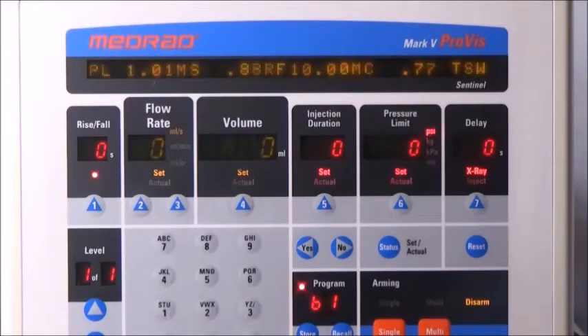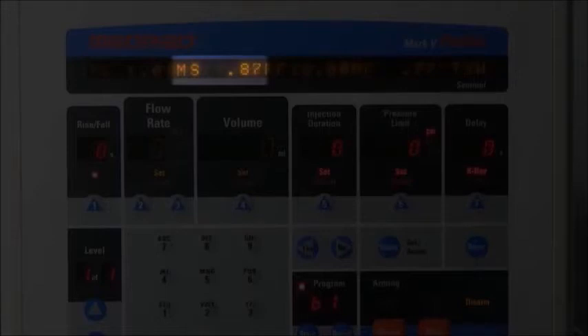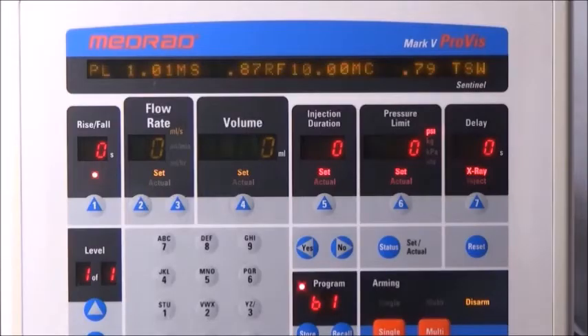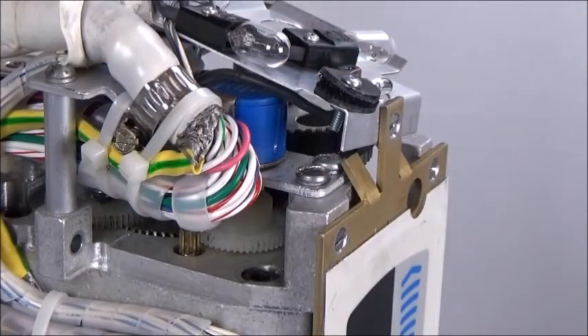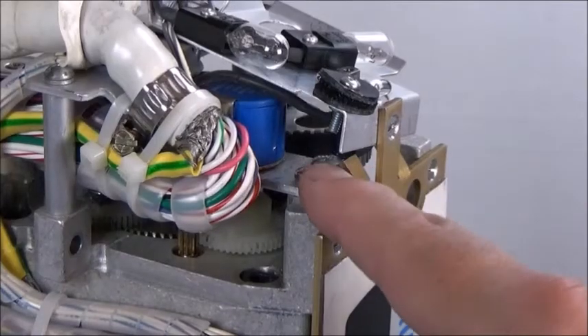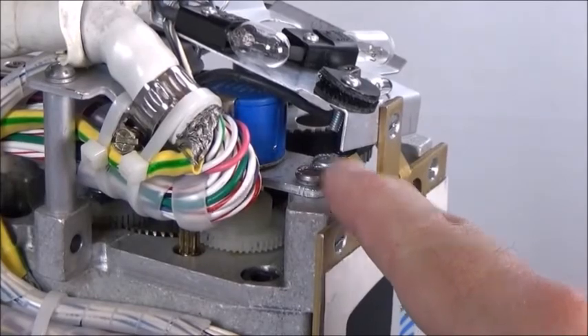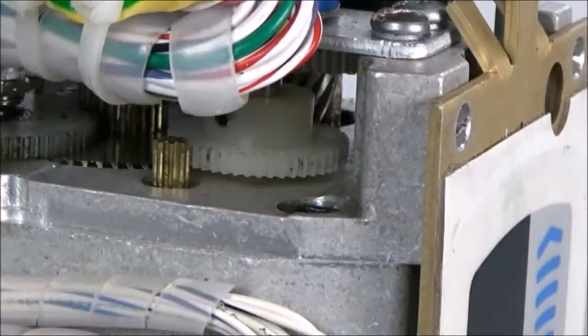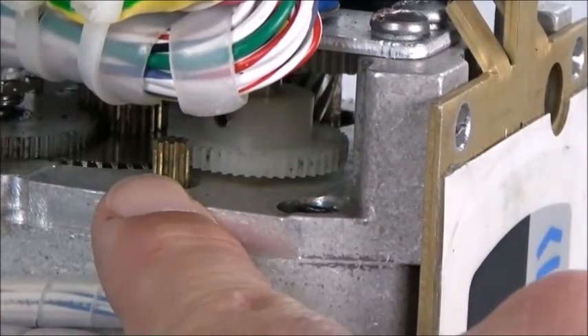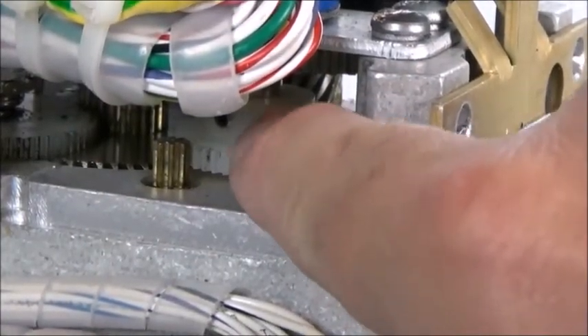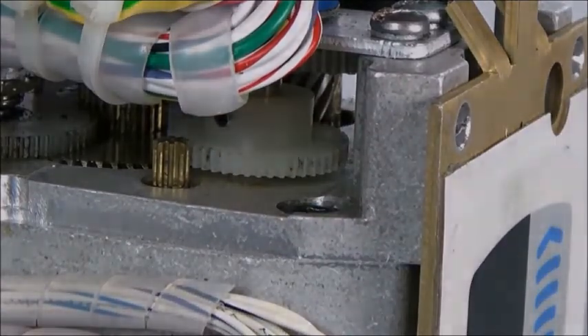Now observe the MS reading on the display. It should be 0.86, 0.87, or 0.88. If necessary, we will adjust R2 in the same manner you adjusted R1. You will need to remove the metal plate covering R2, loosen the two screws holding R2 in place, and adjust its gear to get an MS reading of 0.86, 0.87, or 0.88, then tighten R2 back down. When finished, ensure the MS pot gear is in contact with the brass gear but has some wiggle to it. Do not move the plates or reattach the MS motor lead just yet.